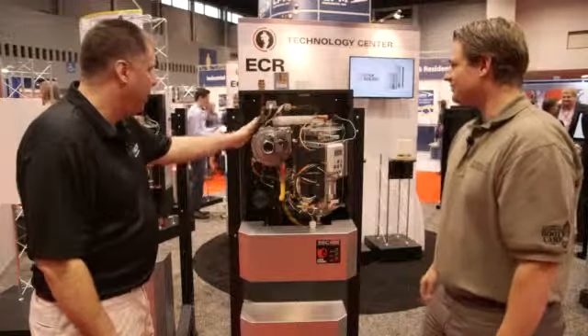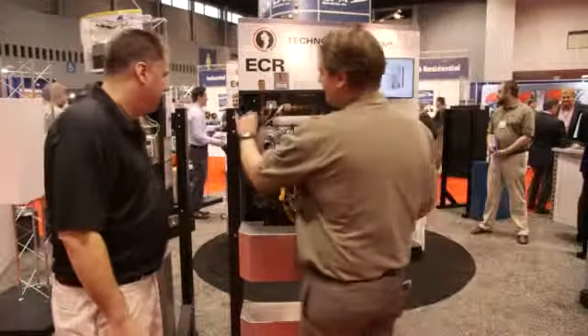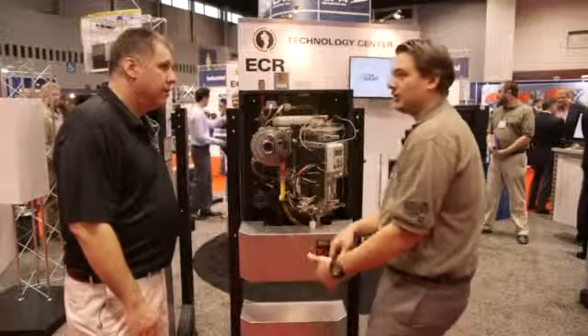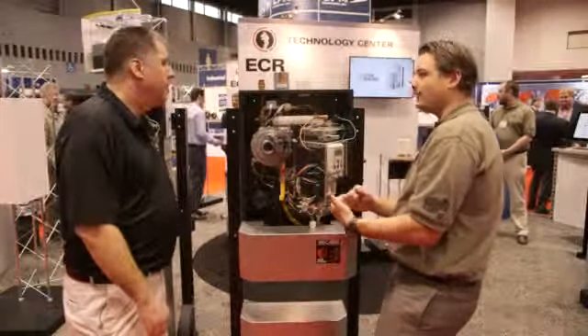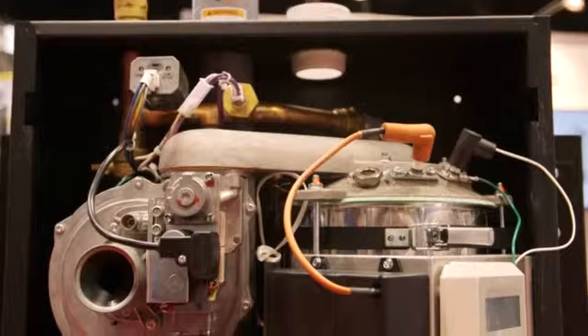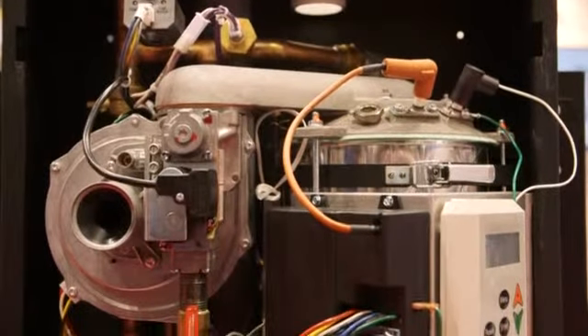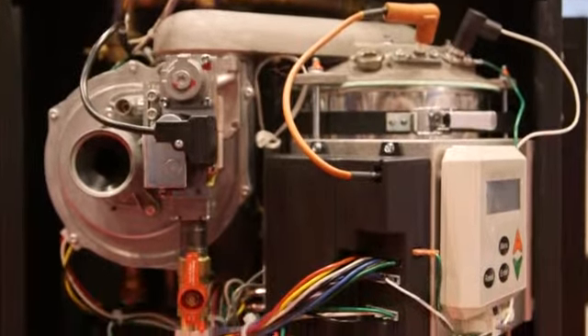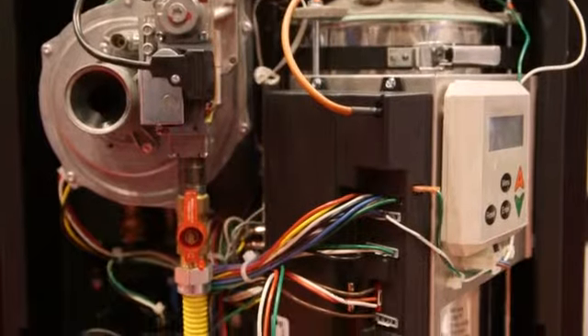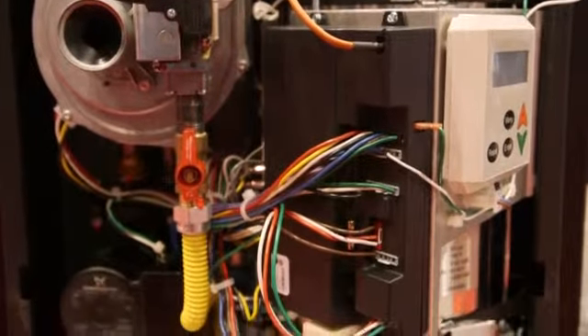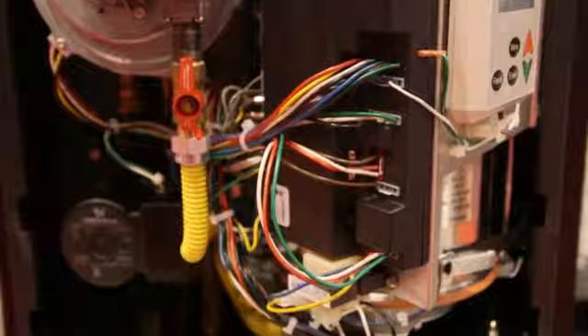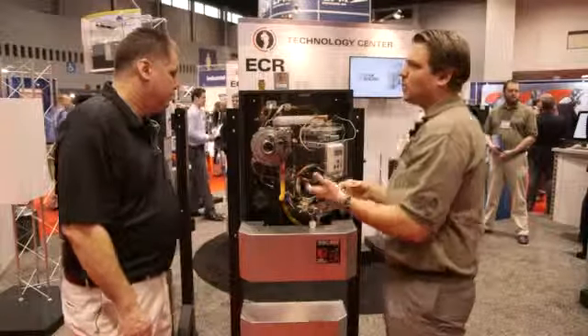What's the purpose of the ball valve here then? The ball valve here is if you ever wanted to do external primary secondary, you could shut that off and put some tees outside of there if you need to. If you're into the replacement market or you just wanted to do it yourself. So this gives you a lot of flexibility. It's very flexible. We also use that for purging purposes. It can be hard to get the air out of these boilers, so if you shut that off, it forces the water through the heat exchanger.